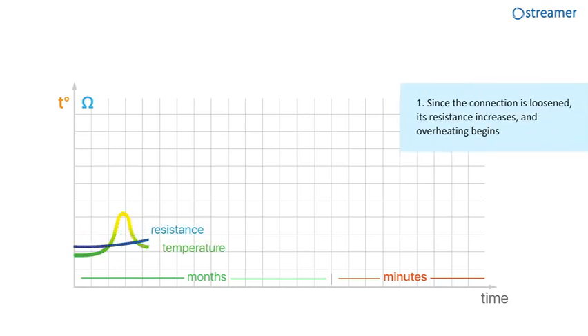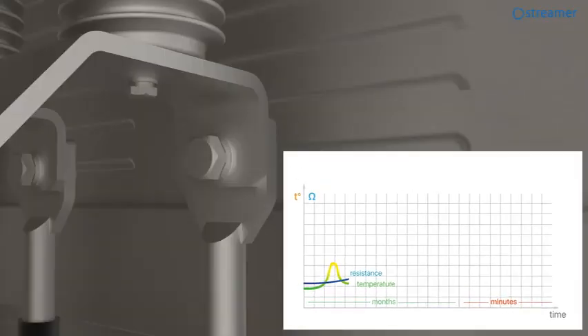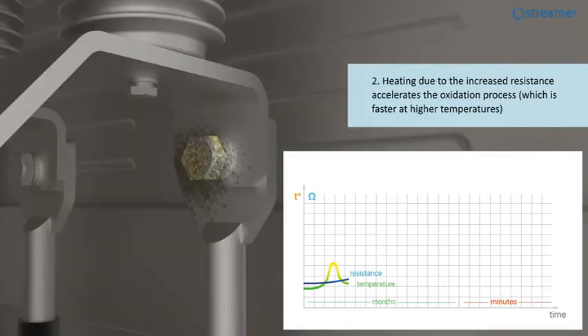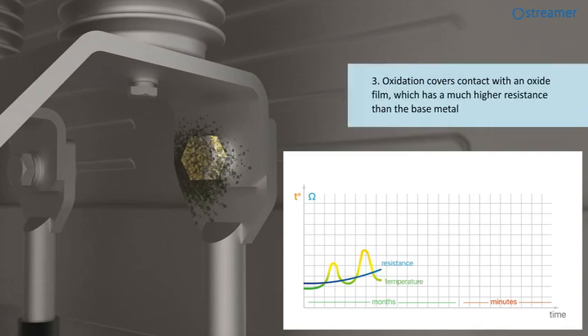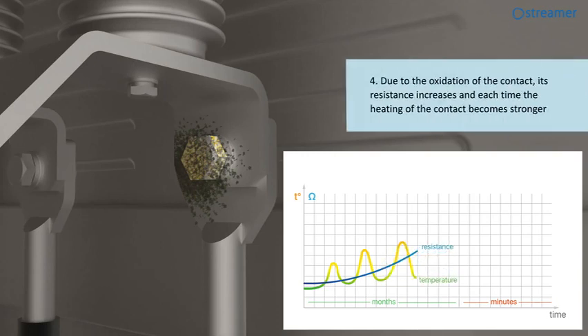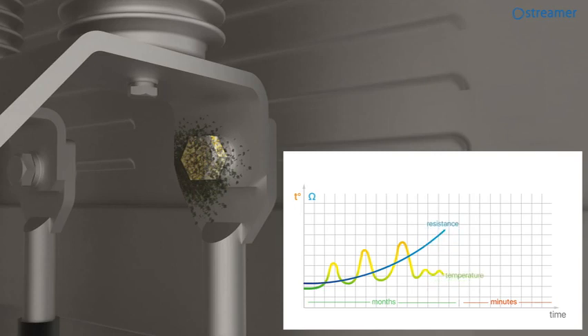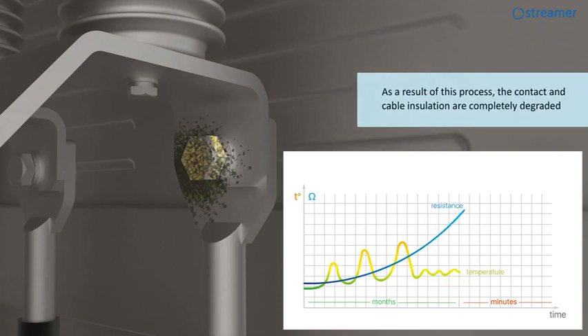Since the connection is loosened, its resistance increases and overheating begins. Heating due to the increased resistance accelerates the oxidation process, which is faster at higher temperatures. Oxidation covers the contact with an oxide film, which has a much higher resistance than the base metal. Due to the oxidation of the contact, its resistance increases, and each time the heating of the contact becomes stronger. As a result of this process, the contact and cable insulation are completely degraded.